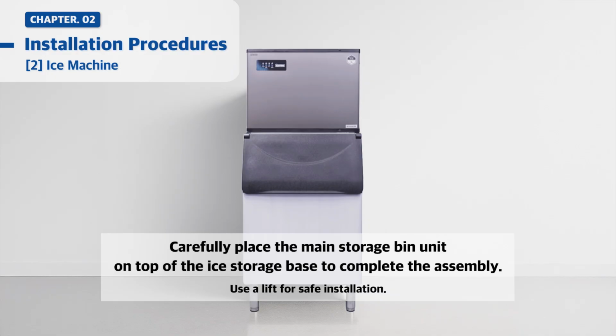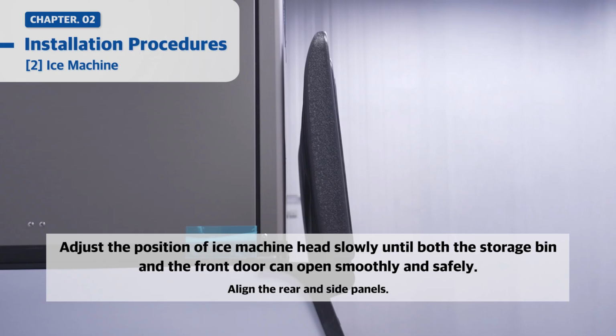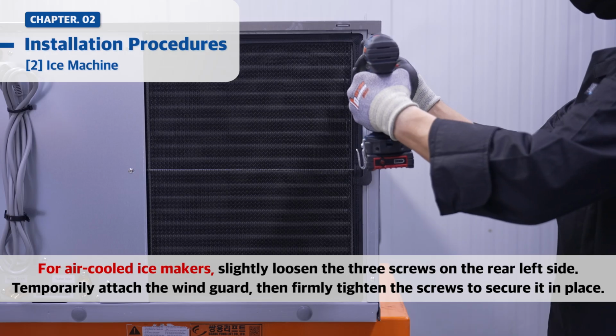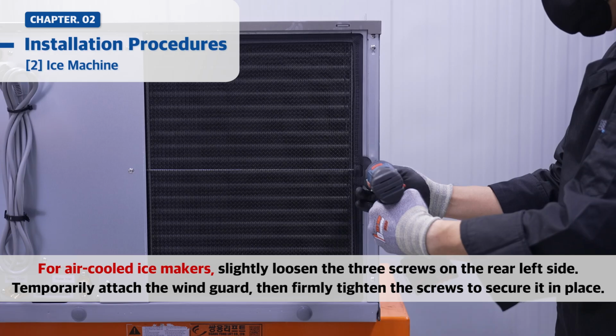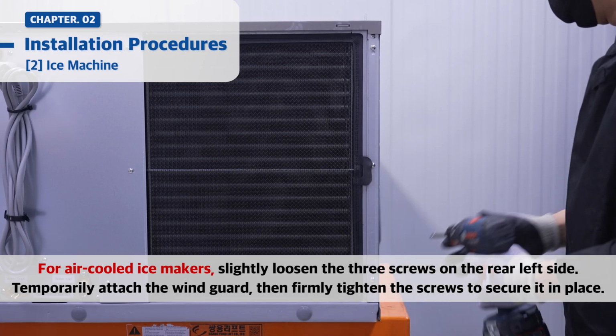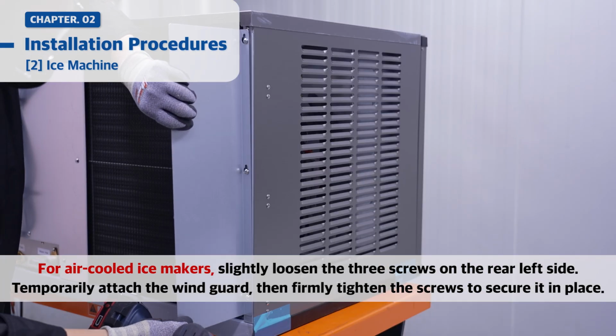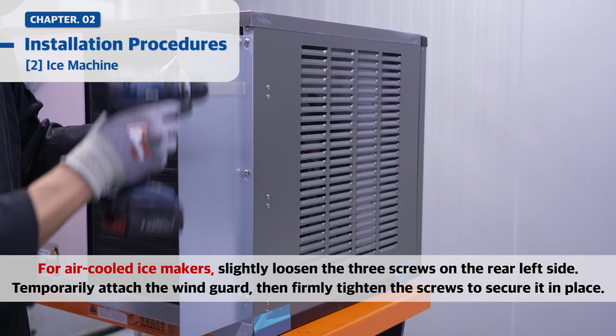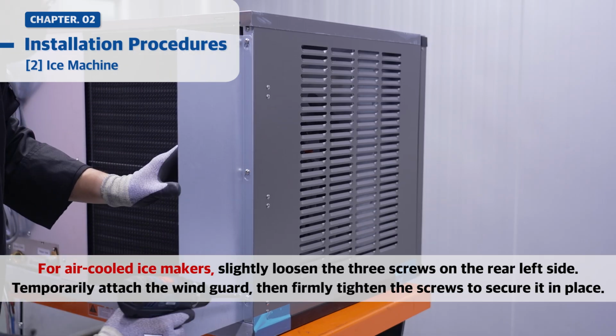Carefully place the main storage bin unit on top of the ice storage base to complete the assembly. Adjust the position of the ice machine head slowly until both the storage bin and the front door can open smoothly and safely. For air-cooled ice makers, slightly loosen the 3 screws on the rear left side. Temporarily attach the wind guard, then firmly tighten the screws to secure it in place.